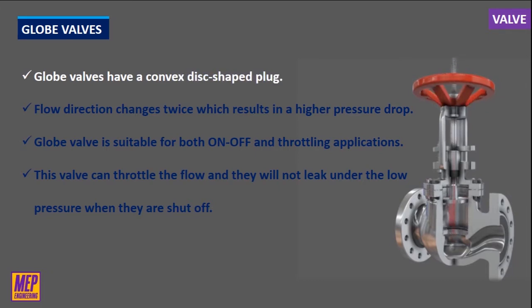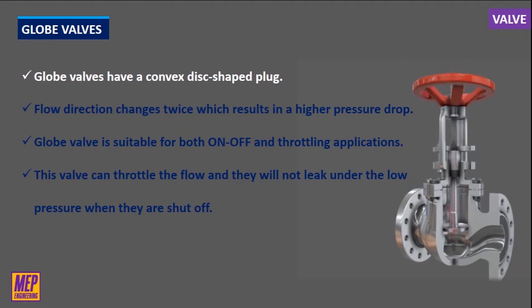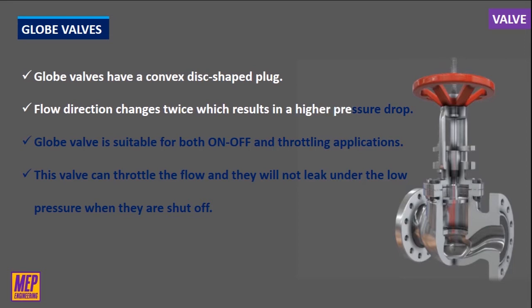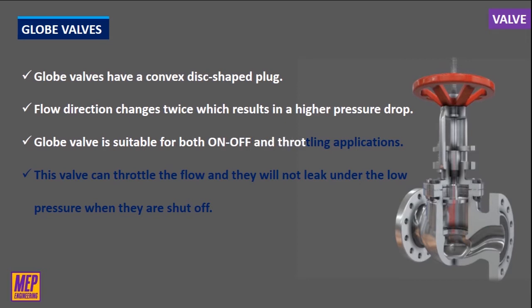Globe valves have a convex disc-shaped plug which raises and lowers via a rising stem into a circular seat around the inside of the globe-shaped body. The flow of fluid through the globe valve has an S-shaped path. Due to this, the flow direction changes twice, which results in a higher pressure drop.